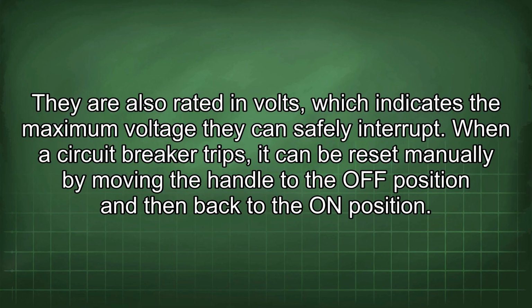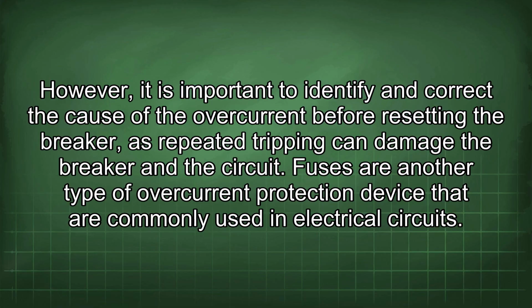When a circuit breaker trips, it can be reset manually by moving the handle to the OFF position and then back to the on position. However, it is important to identify and correct the cause of the overcurrent before resetting the breaker, as repeated tripping can damage the breaker and the circuit.